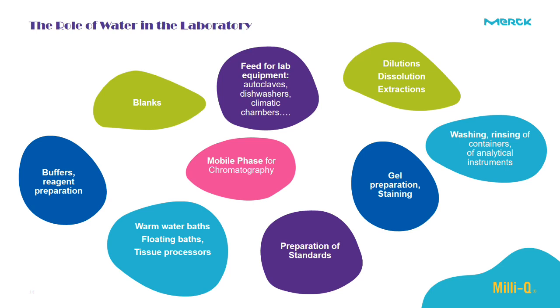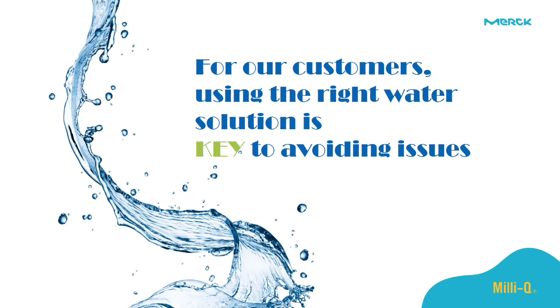The quality of pure and ultra-pure water is very sensitive to the atmosphere. Water usually works as a magnet for the different types of contamination that may exist inside the lab. So storing pure and ultra-pure water is not recommended at all. Using freshly prepared ultra-pure water is the key solution to avoid issues that may happen during the experiments or the applications we are using the water for. Accordingly, my colleagues Mohamed and Elmallah will review in the next slides the impact of contaminations and impurities in the water you are using on the instrument, on the data interpretation, and even on the results you are expecting to get.